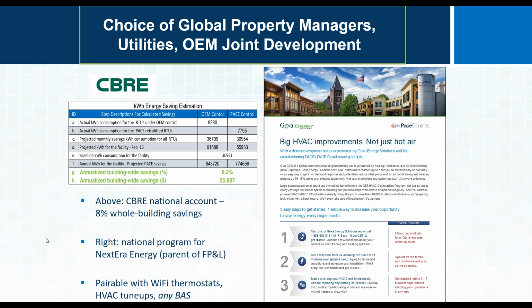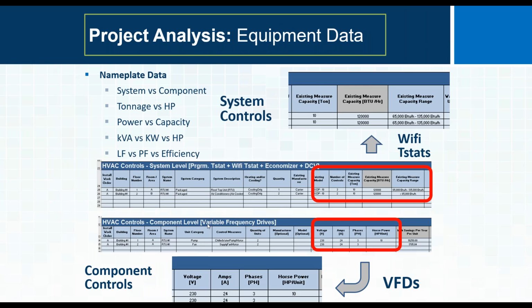As this node is installed, you're picking up supply and return temperature and full power demand. The technician can do a visual inspection of the coil, filter, and contactors and enter all this data. With 3 quick scores and about 10 minutes of work, he can do an HVAC snap diagnostic to determine whether that unit could use a tune-up. That makes a big difference — when you've got a technician there with the tools, why not do the tune-up if it needs it?